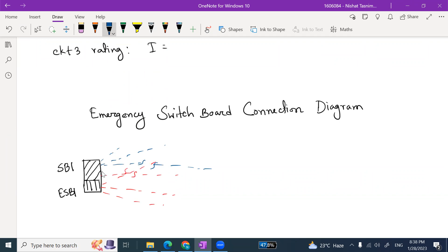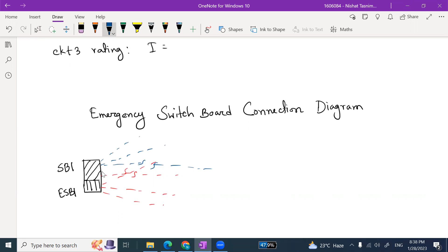So if there are overlaps, we use an S sign, and blue color for normal connections. Did you understand what I said? You will not use separate switchboards for emergency connections. You will use the same switchboard, but inside this switchboard there will be connections coming from both the generators and the main grid.